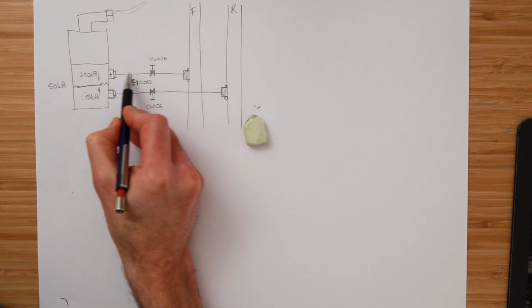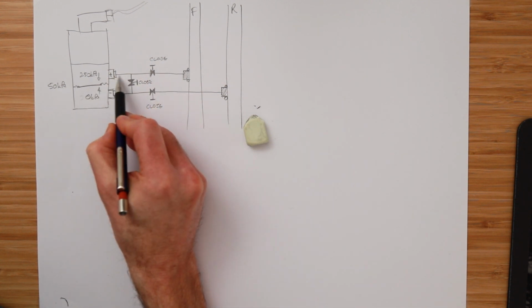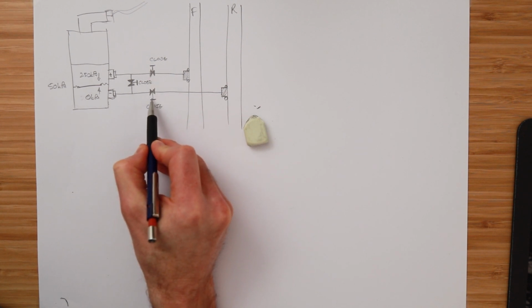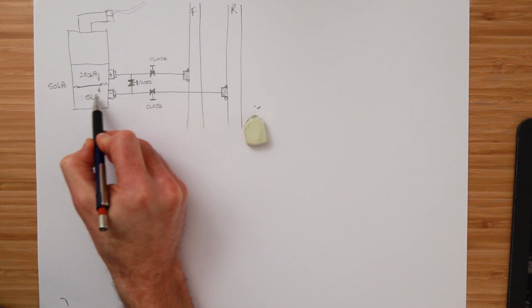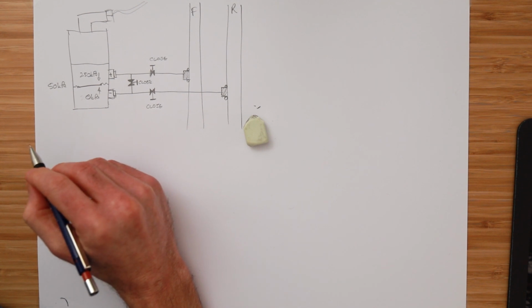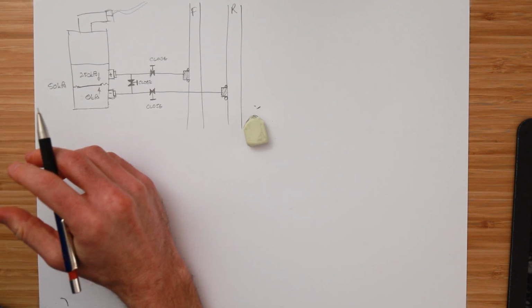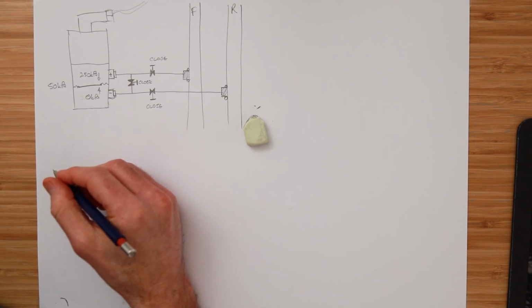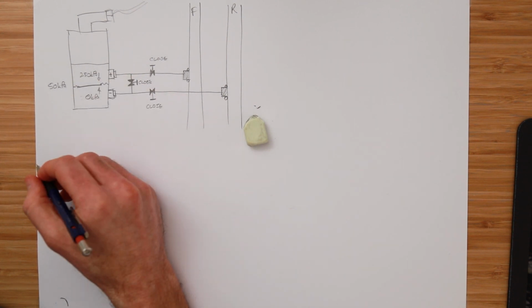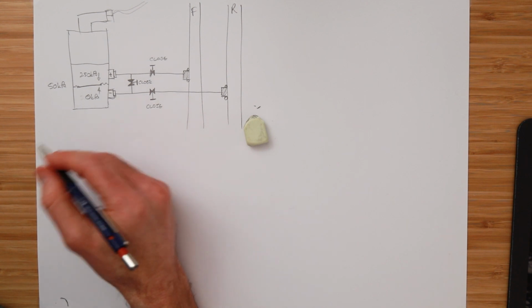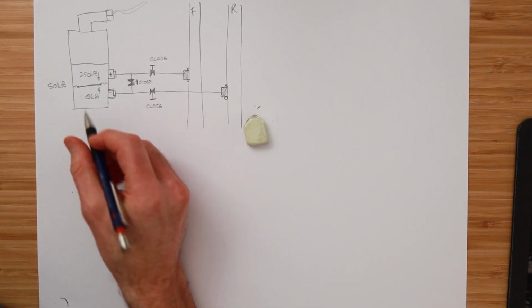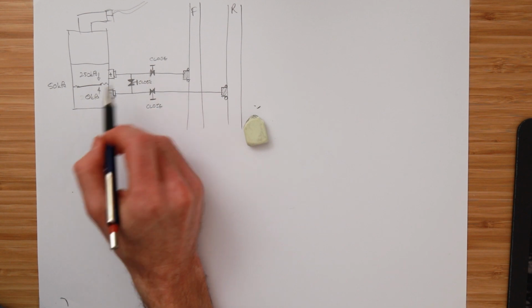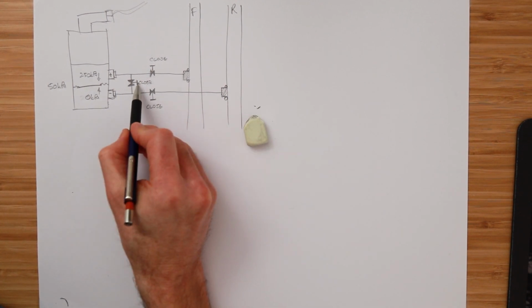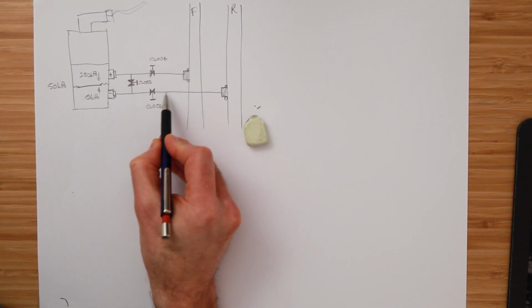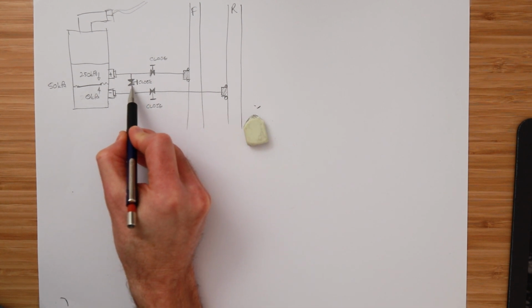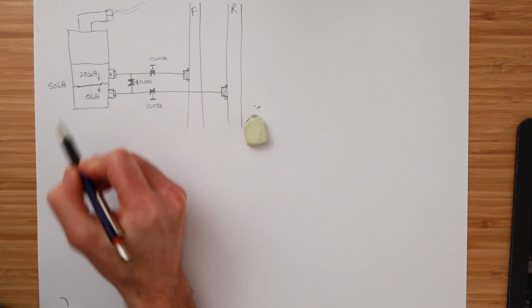That full static pressure comes through here, bursts the diaphragm. He checks there's no leaks. Then he opens this valve and the water pressure comes through. He checks there's no leaks. I've had it before where when the chillers are in the basement and there's a large head above, I've had it that every single pressure transmitter across the 3 chillers' evaporator, the mechanical pipe fitter bursts the diaphragm when he does the leak test. It doesn't matter which one you open. If this is closed and you open this one first, all the pressure comes through, it all comes into here, it bursts the diaphragm.